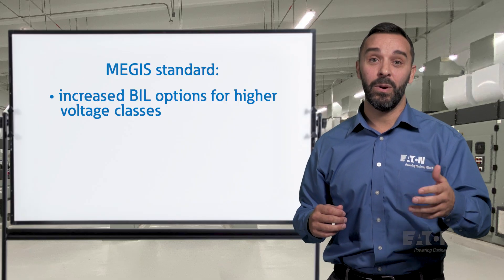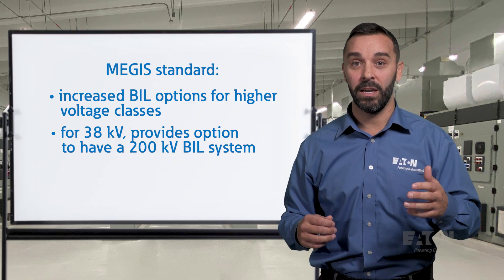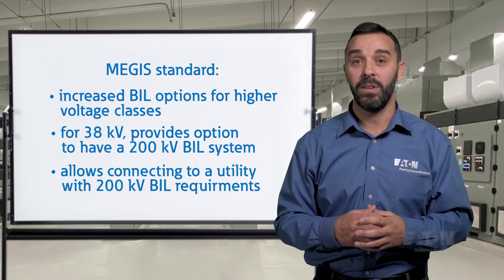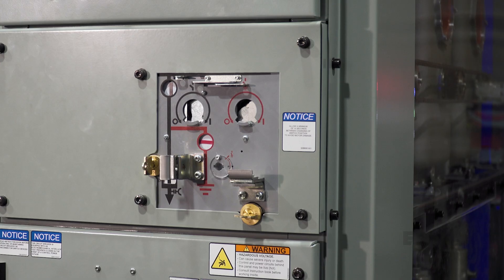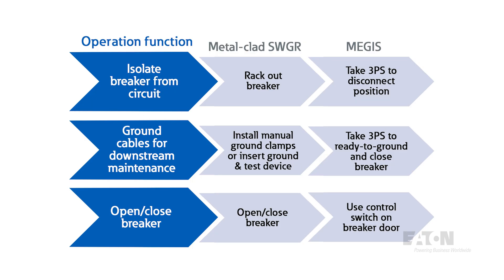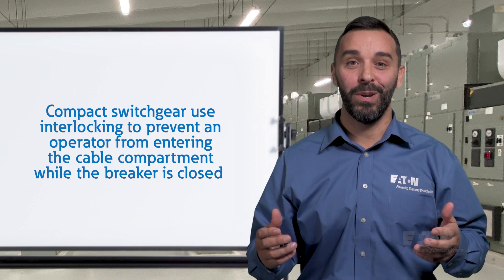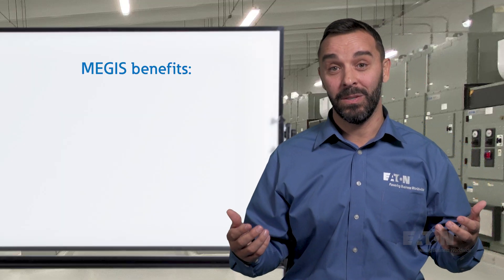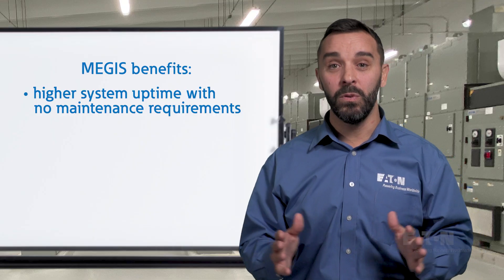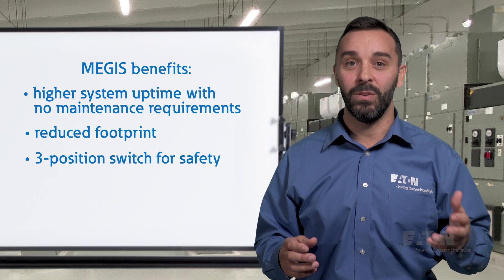For example, the MEGIS standard for 38 kV provides the option to have a 200 kV BIL system, where the metal-clad switchgear standard is only 150 kV BIL. This allows you to connect to a utility with 200 kV BIL requirements. Unlike metal-clad switchgear which utilizes draw-out breakers to isolate the circuit, MEGIS uses a three-position switch to connect or disconnect the breaker from the main bus. The final position in the three-position switch allows you to ground the connected line or load cables through the closed circuit breaker. To safely access the cable compartment, interlocking is required with the main breaker to prevent an operator from entering the cable compartment while the breaker is in the closed position.